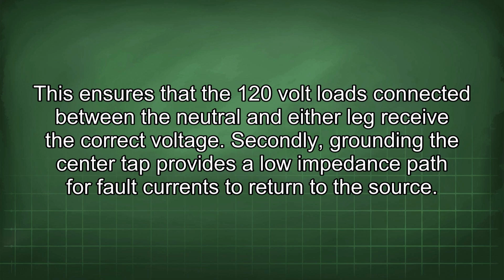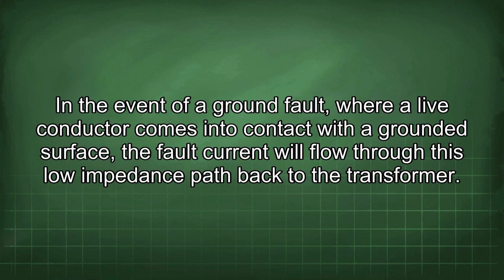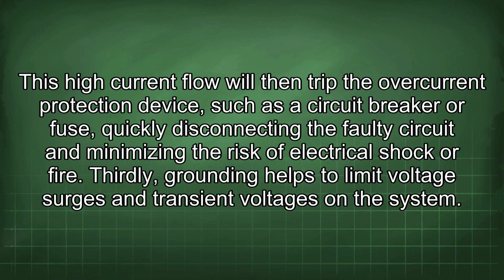Secondly, grounding the center tap provides a low impedance path for fault currents to return to the source. In the event of a ground fault, where a live conductor comes into contact with a grounded surface, the fault current will flow through this low impedance path back to the transformer. This high current flow will then trip the overcurrent protection device, such as a circuit breaker or fuse, quickly disconnecting the faulty circuit and minimizing the risk of electrical shock or fire.